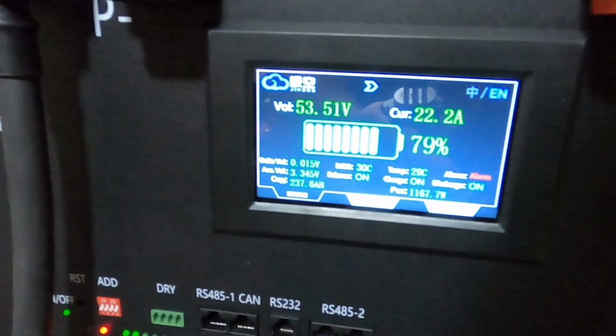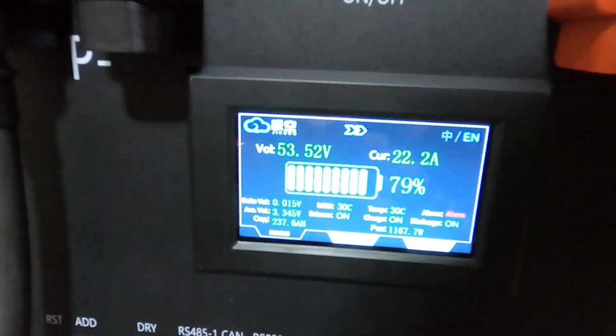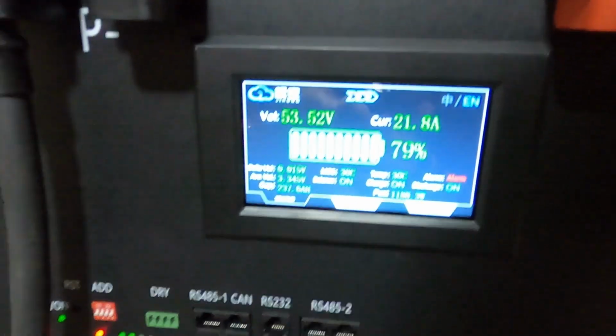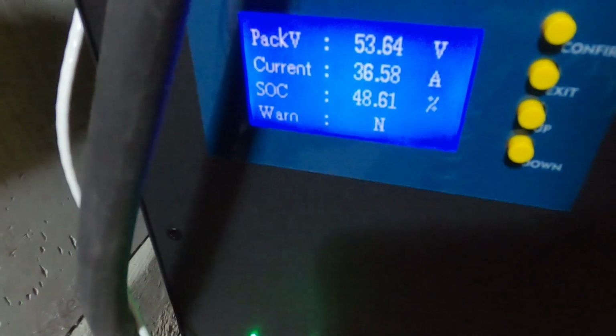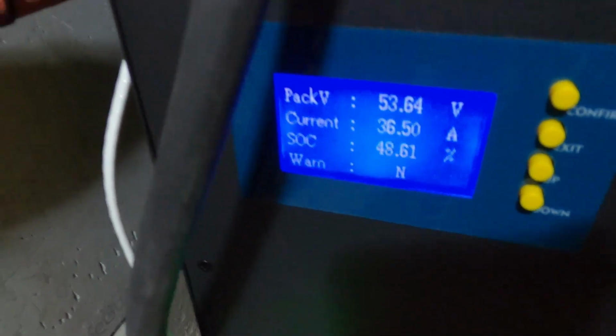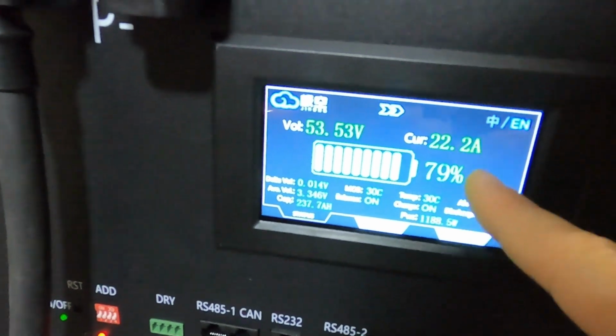So with JK BMS, we're getting 22.2 amps. And our Seplos BMS, we're getting 36.58 amps. Look at the state of charge on this. This is not accurate. Once we reach the reset state of charge conditions, the state of charge will be accurate. We're going to come back when the batteries have reached 55.2 volts, and we'll see where we're at when we're floating, and then we'll go ahead and switch the battery to the small charger and do our top balance.